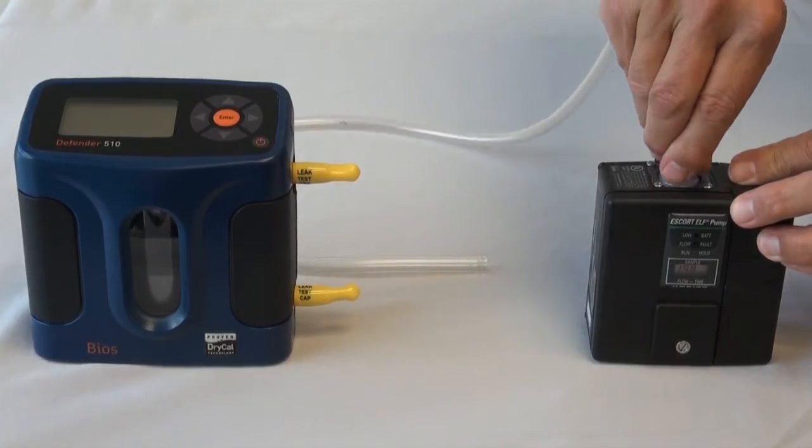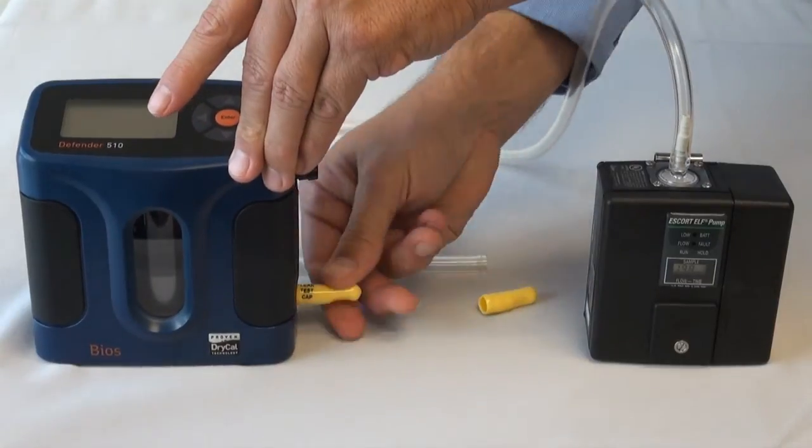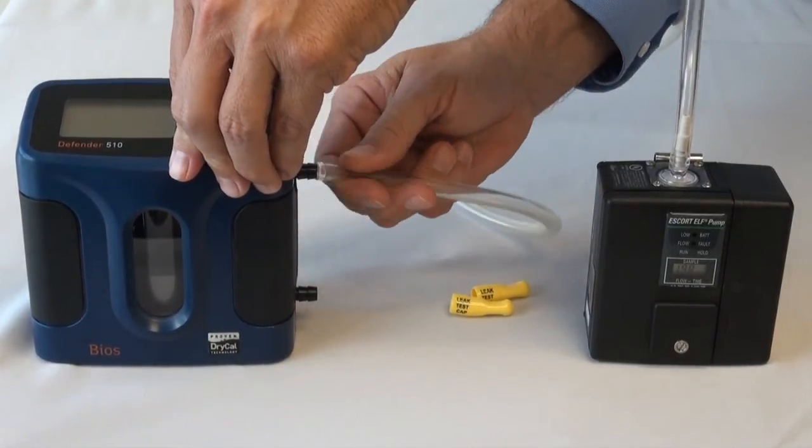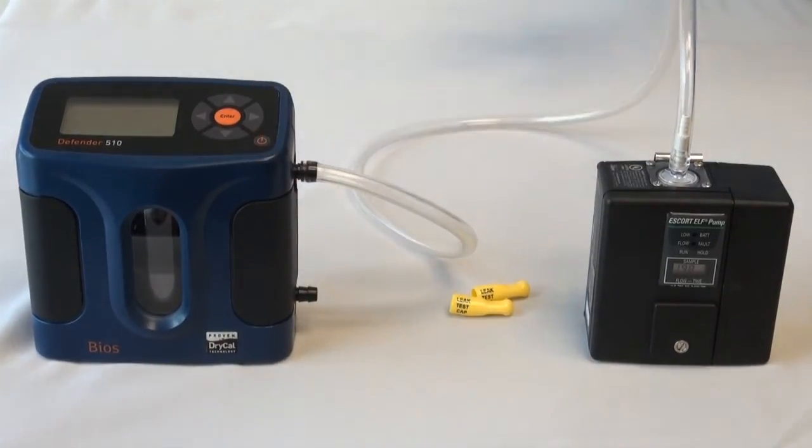Failure to use the restrictor can result in a calibration inaccuracy. Place the restrictor in line of the sampling hose between the pump and the sampling media. The calibration procedure from this point is the same as with the Zefon Digi-Cal.